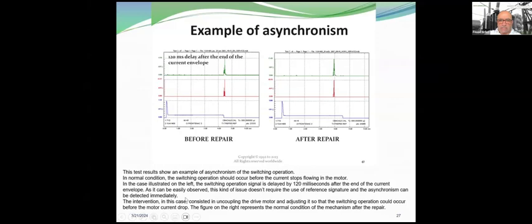And the intervention in this case consisted of uncoupling the drive motor and adjusting it so that a switching operation could occur before the motor current drop. And the figure on the right represents the normal condition of the motor of the mechanism after the repair.